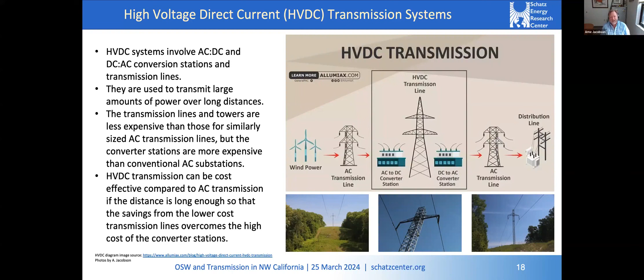The transmission lines and towers for HVDC systems are less expensive than those for similarly sized AC systems, but the converter stations for HVDC conversion are more expensive than conventional AC-based substations. So HVDC transmission can be cost-effective compared to AC transmission if the distance you're trying to deliver power over is long enough so that the savings from the lower cost transmission lines overcomes the high cost of the converter stations. As we talk a bit later in the session, we'll refer back to AC and high voltage DC transmission. I wanted to provide a little background on all of that.